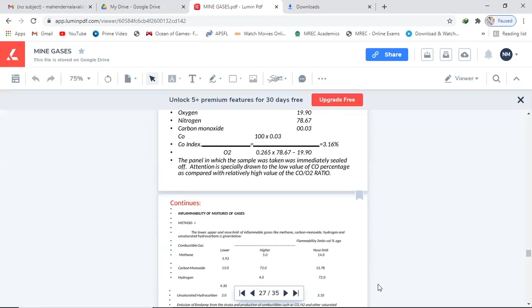Continues, that is the inflammability of a mixture of gases. Graphical method. So how can we find? We can also interpret the fire by using the graphical method, based on effective combustibles and effective inert gases. This method takes into account three features of mixtures of fire gases. The effective inert component is defined as excess N2 plus 1.5 CO2 volume percent. And the effective combustible component is defined as CH4 plus 1.25 H2 plus 0.4 CO, and the ratio R, that is, total combustibles.